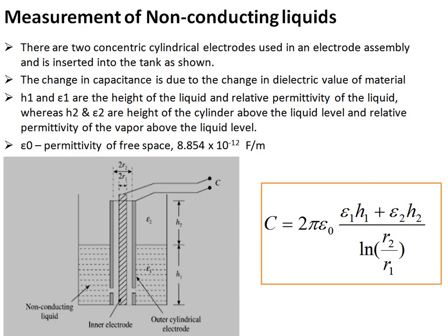The effective capacitance is given by C = (2π·ε₀ / ln(r₂/r₁)) · (ε₁·h₁ + ε₂·h₂). As h₁ rises, the capacitance increases because the dielectric constant of the liquid is much higher than that of air or vapor. This is the operating principle for non-conducting liquids.